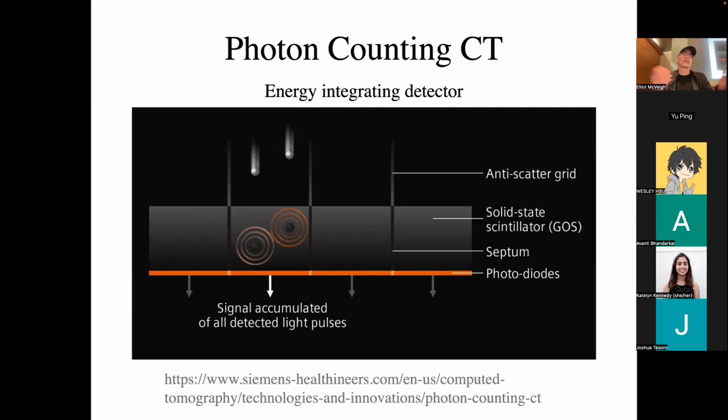There are a lot of designs of these materials such that the flash is very bright or very short-lived, etc. That light flash is contained inside a little square detector, and you have mirrored elements on the wall so that the light stays inside that one detector that you've caused the flash in. You don't want it to leak out to the neighboring detectors. So these septa between the active elements basically isolate it and make the flash stay inside.